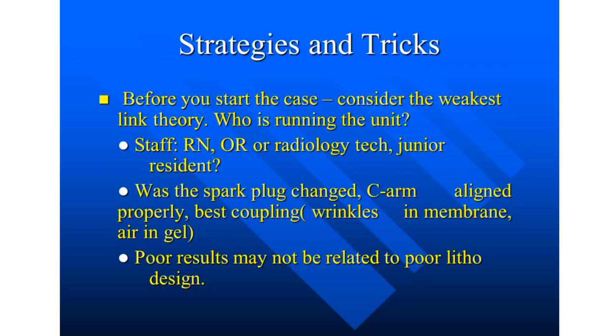But as the attending physician, I'd like to be in the room, making sure that it's set up correctly, making sure that if it's a spark gap, the spark plug was changed, making sure that the water in the unit, if it needs water for the membrane, has been changed. I want to make sure that the C-arm alignment has been done correctly so that I know that F2 is at the correct point, so that I'm going to get good fragmentation of my stone.